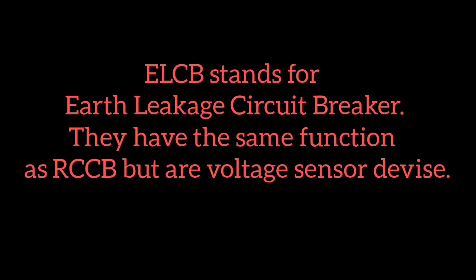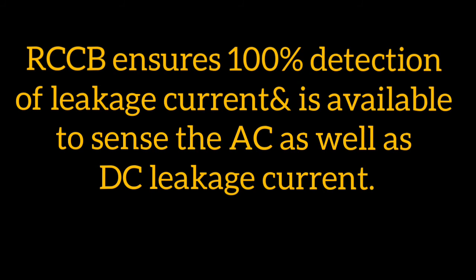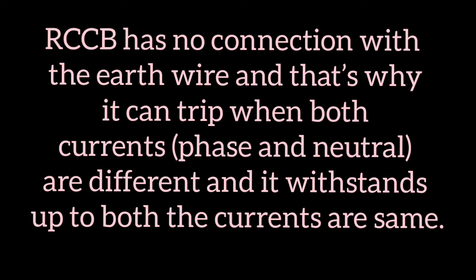The first big difference between RCCB and ELCB is their full form. RCCB stands for Residual Current Circuit Breaker, whereas ELCB stands for Earth Leakage Circuit Breaker. RCCB is a newer name and refers to a current operated device, whereas ELCB refers to a voltage operated earth leakage device. RCCB ensures 100% detection of leakage current and can sense AC as well as DC leakage current, whereas ELCB is not preferable as it can only detect current that flows back through the main earth wire. RCCB has no connection with the earth wire, and that's why it can trip when the phase and neutral currents are different, and it stays on when both currents are the same.